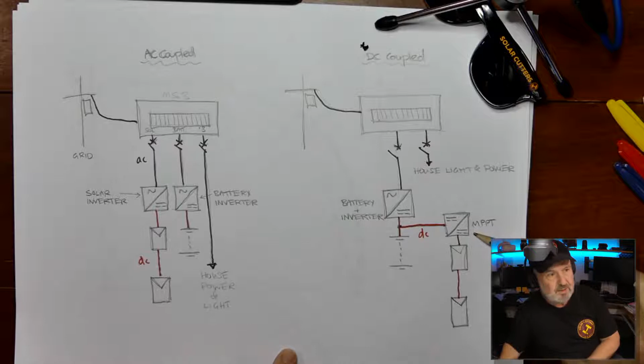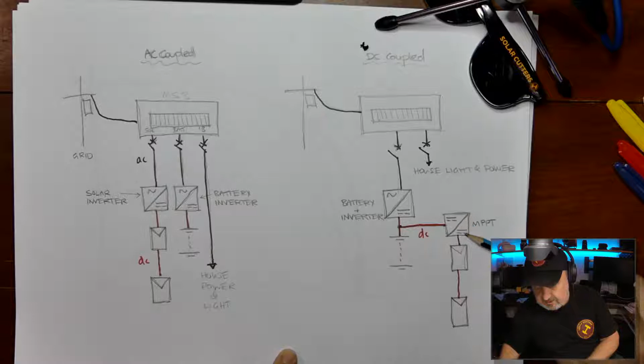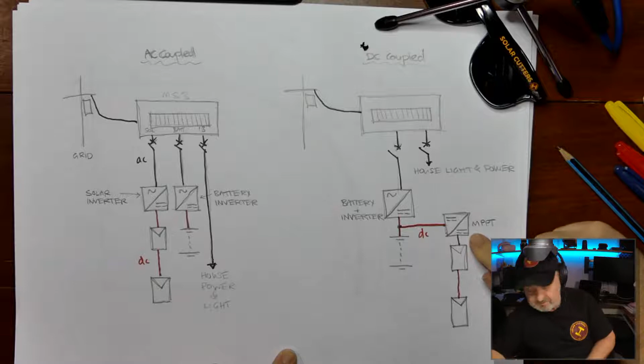Now you'll notice the symbol here for the maximum power point tracker looks very similar to an inverter symbol, but the little dash lines mean DC, as opposed to the sinusoidal line meaning AC. So this MPPT is effectively a DC to DC conversion device. The reason it converts is it's converting voltage and current to match that of the battery. So the PV array might be working at several hundred volts, whereas the battery might be working at 48 volts. And the magic of the MPPT is it does the maximum power point tracking, but also the voltage matching to suit the load, in this case a battery.